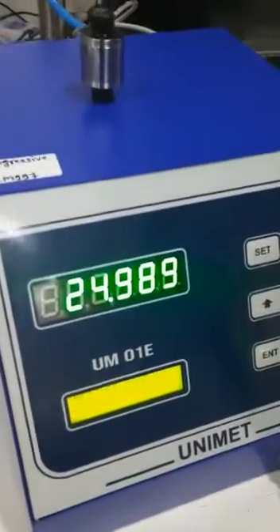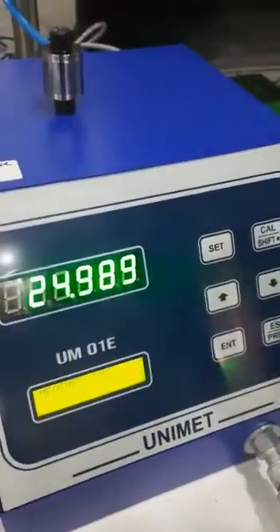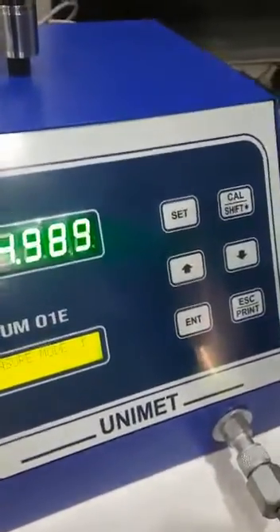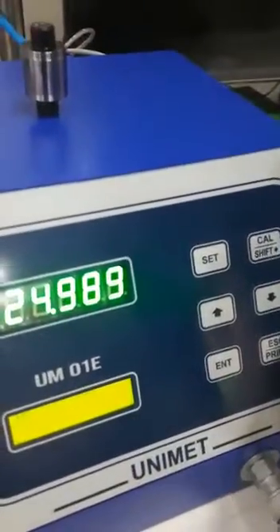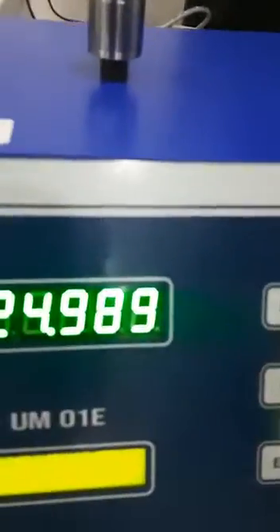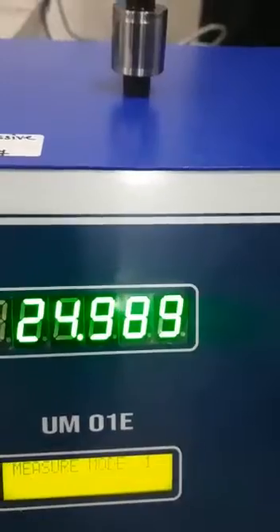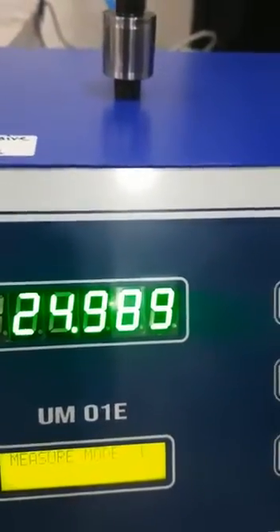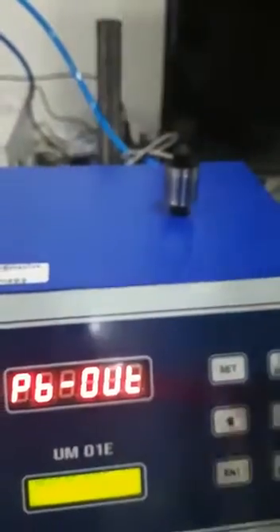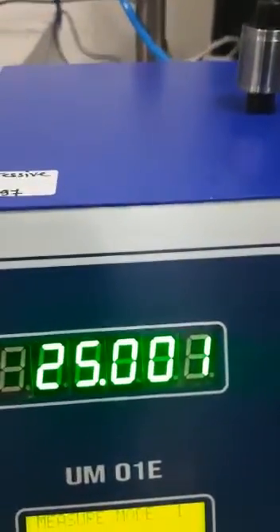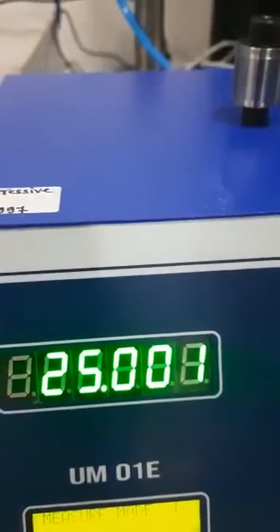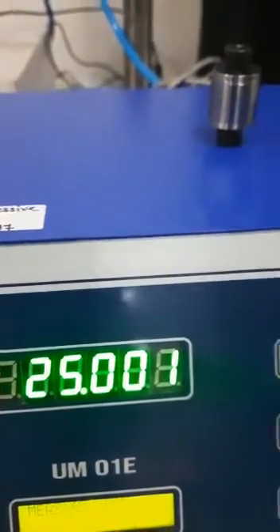Now I will show the absolute value. The absolute value we entered was 24.996, and with the low master, which is minus 7 microns, it is showing 24.989. For the high master, it will show 25.001, which is 5 microns plus. Now this is the master setting done.